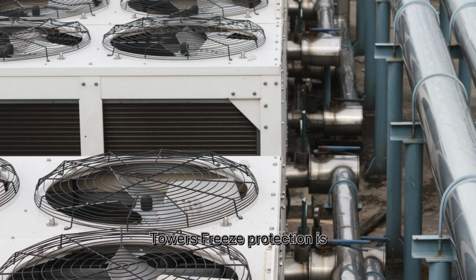Freeze protection for cooling towers. Freeze protection is critical in any climate that experiences sub-freezing temperatures. For open tower systems, ensure that basin heaters are installed and controlled by a thermostat at 40 degrees Fahrenheit. A low water cutoff prevents heater burnout. Heat trace and insulation are applied to exposed piping. Fans have vibration cutoffs to prevent damage from ice buildup. For closed-circuit towers, additional protection includes positive closure dampers to prevent heat loss, circulating the loop pump during cold periods, using glycol mixtures to lower the freezing point, and continuous monitoring through the BMS to ensure the coil doesn't freeze.